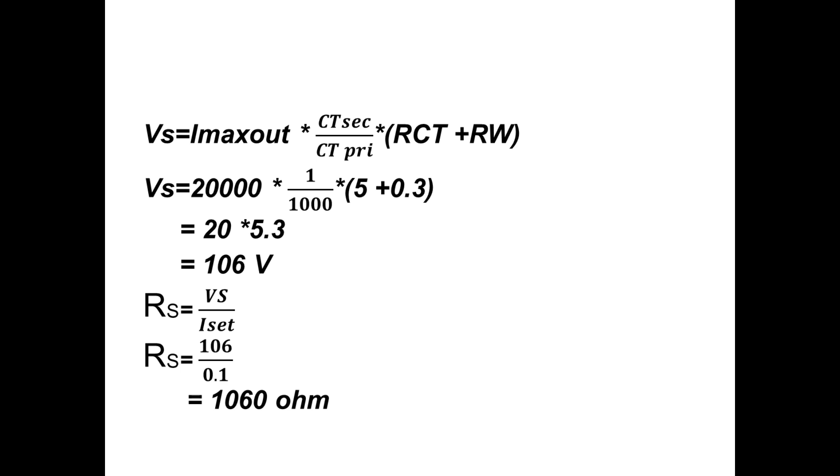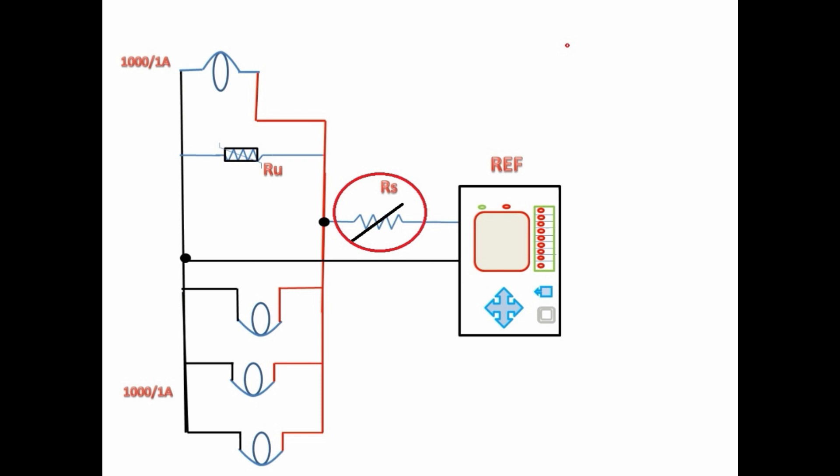We have to note here. Depend on the REF protection pickup, i.e. ISET, the resistor value will change. So, this resistor normally will choose variable resistor.